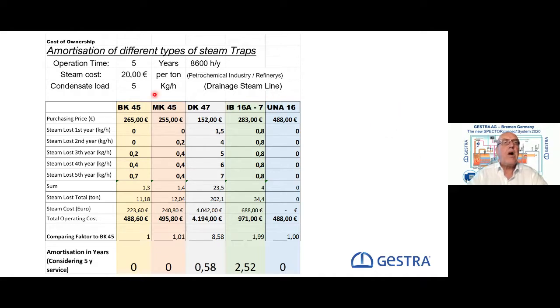So we look at an operation time of 5 years, 8,600 hours a year. Steam costs are rather low. For the petrochemical industry and refineries, we consider 20 euro per ton of steam. You need round about 700 kilowatt hours per ton of steam, and then you can calculate that you need round about 65 cubic meters of natural gas, or round about 50 liters of diesel oil for 1 ton of steam. You can calculate your steam price from your local costs.